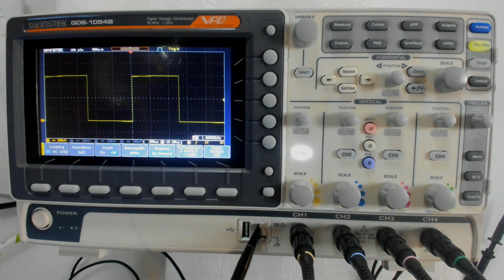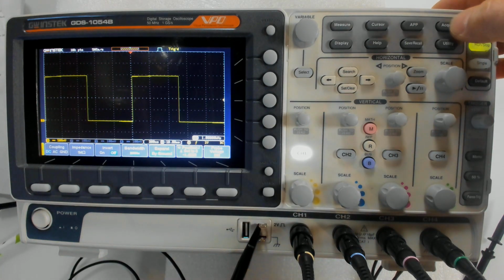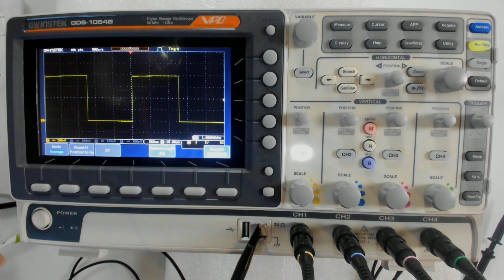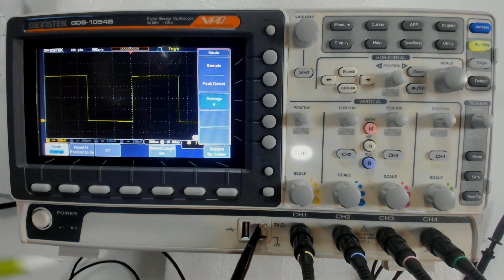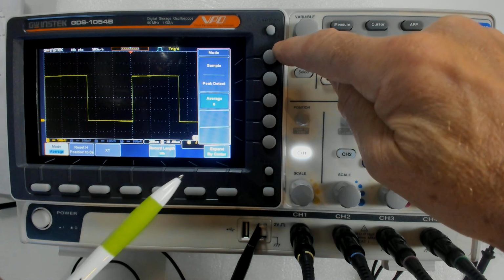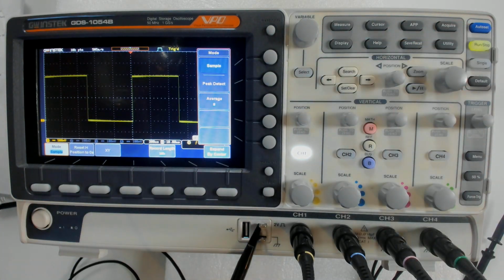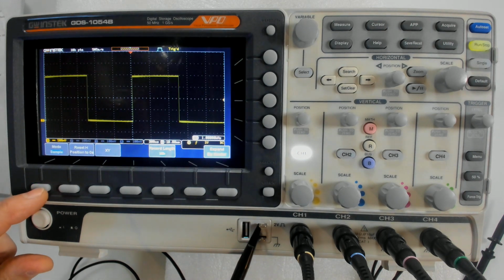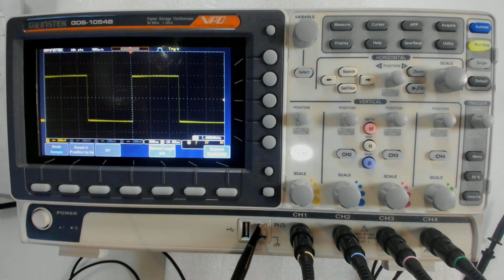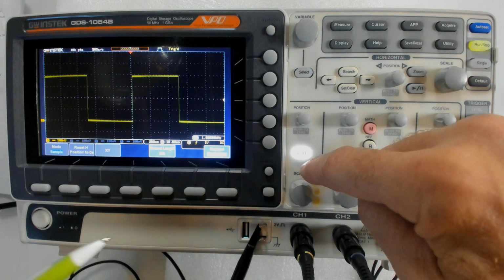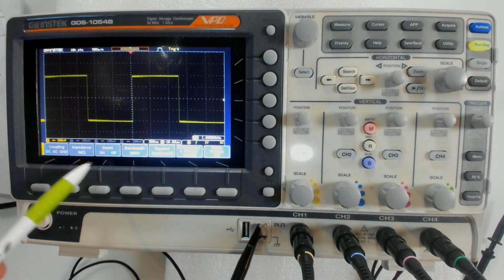And now that I've got the probe compensated, I am going to take the averaging off because for other things I want to watch, I want to see how noisy they are as a point of interest. I mean, if it's a really noisy signal, I want to know about it. So I'm going to go up to the acquire button here. And remember, it shows me that it's in averaging mode, and that's highlighted. So I'm going to take it back to just sample mode, which will be this soft key here. There we go. Now it's showing sample mode, and I think we're good. Yeah, sample mode. If I want to get back to my channel menu display, I just hit the channel button. I'm back to this display here.